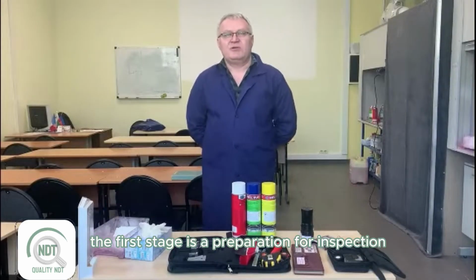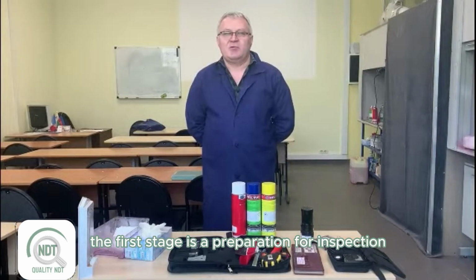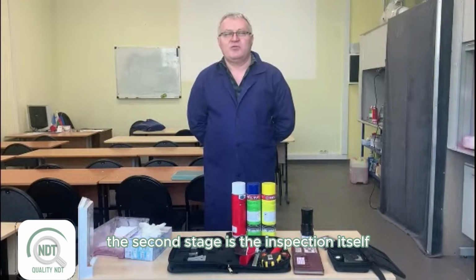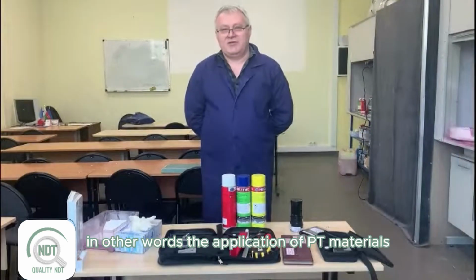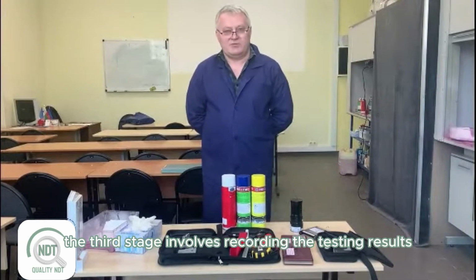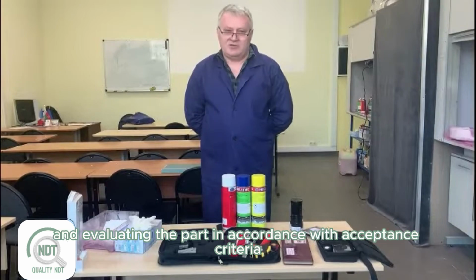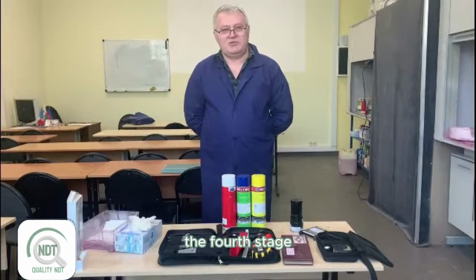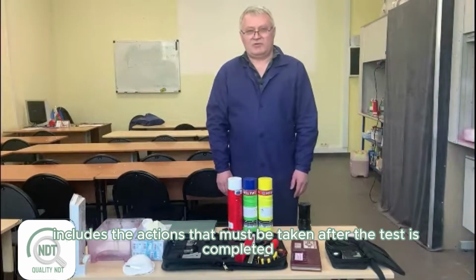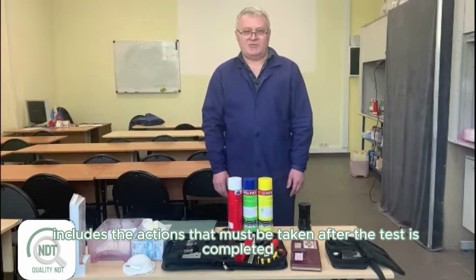The first stage is a preparation for inspection. The second stage is the inspection itself, in other words, the application of PT materials. The third stage involves recording the testing results and evaluating the part in accordance with acceptance criteria. The fourth stage includes the actions that must be taken after the test is completed.